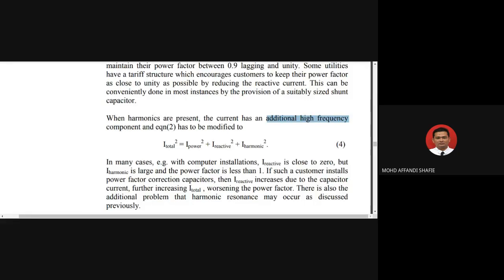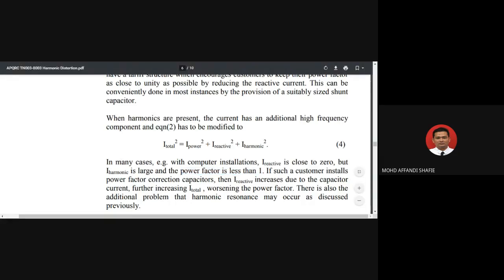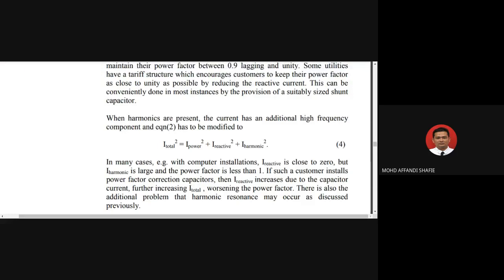In many cases, for example with computer installations, I reactive is close to 0. So in the case of computer installations, I harmonic is large and the power factor is less than 1. So if such a customer installs a power factor correction capacitor, then I reactive increases due to the capacitor current, further increasing I total and worsening the power factor. So this is also an additional problem, that harmonic resonance may occur, as discussed previously.